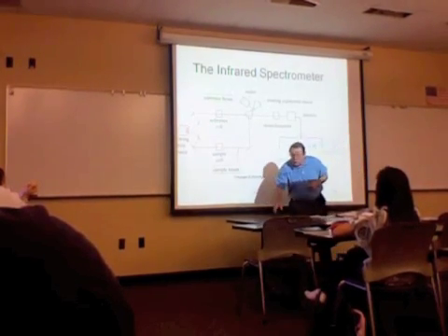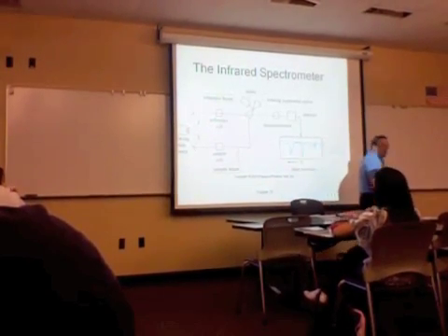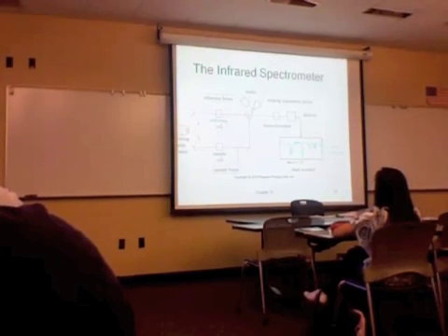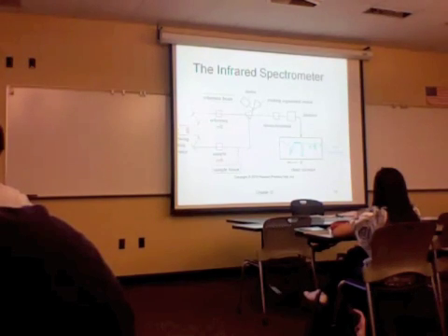These things were notoriously difficult to work with. They were important, and every laboratory had them, but there were a lot of mirrors and optical alignments here that could come out of adjustment. In fact, they'd be sitting on the bench top, and some graduate student would walk up and bump it, and it wouldn't work. And you'd actually have to call service in and have them optically align all of the mirrors and the optical pathway for it to bring it back into adjustment so it would work. These things also took quite a while. They could take anywhere from 20 minutes to 30 minutes to run a scan.